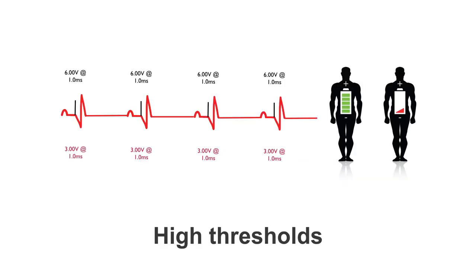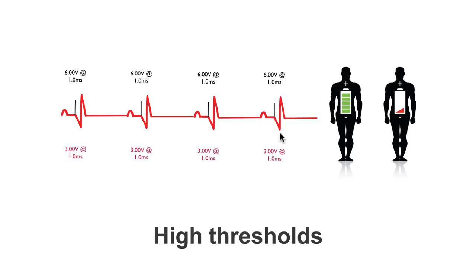What do I mean by this? Well, if we have higher thresholds, something like three volts at one millisecond. To be safe, we would set the pacemaker output pulse to six volts at one millisecond, and we can see that the pacemaker will still perform appropriately. However, using this much energy every time you need to trigger a depolarization will be a huge strain on the battery.